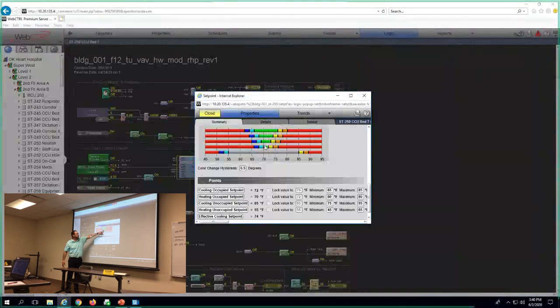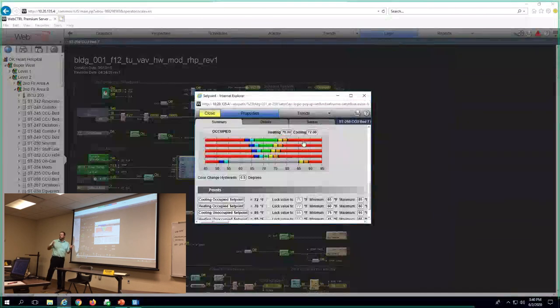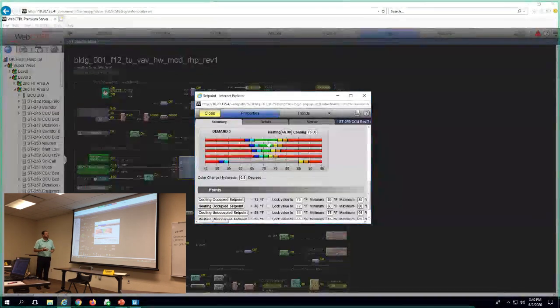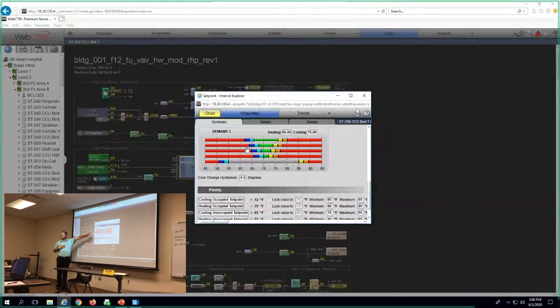It's our normal set point. If you just arrow over to that one, it's demand level 1. If we had an office building and we were trying to do peak demand shedding, if the electric meter went over a certain amount and we needed to knock those set points, it automatically relaxes the set points to keep the utilities underneath a certain peak. It'll do the whole building all at one time. It's very effective, and we've done a lot out in the state of Oklahoma, but you have like 3 demand levels to do it. We're not using those 3 here. It's not part of the sequence, but I want you to know what they are, because it says demand level 1, 2, and 3. Tie the electric meter in, you can relax the deadband on all those zones, and the utility meter will just go down. It's kind of amazing that it actually works the way it does. In a hospital, you don't want to do it because you'll have some patients that are upset.